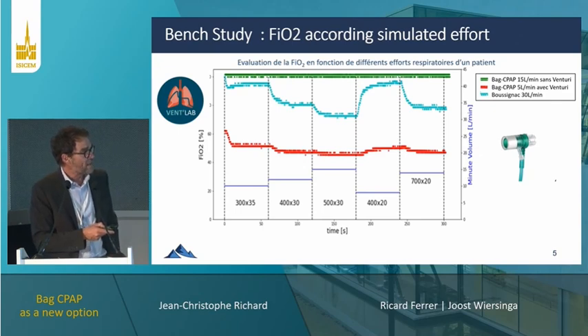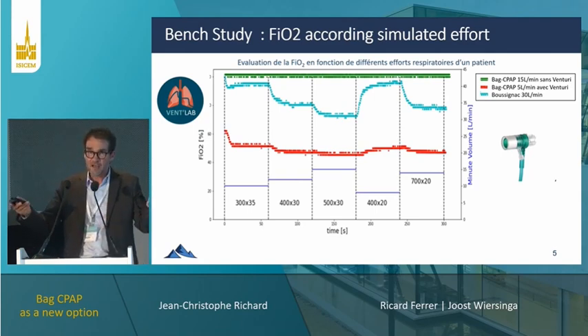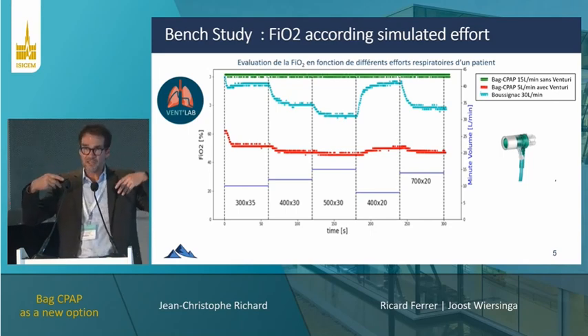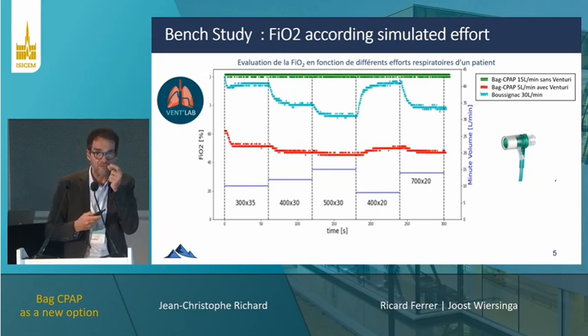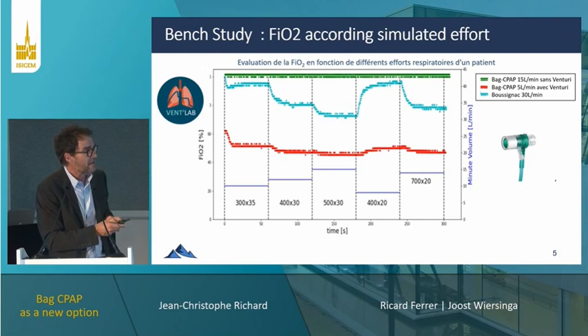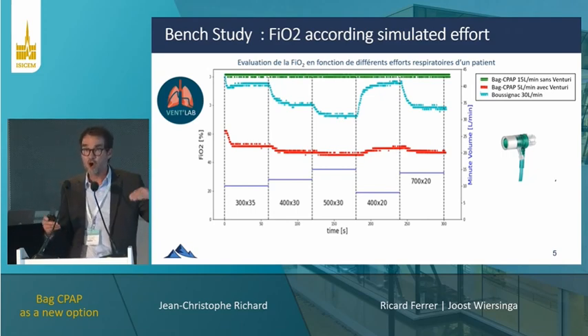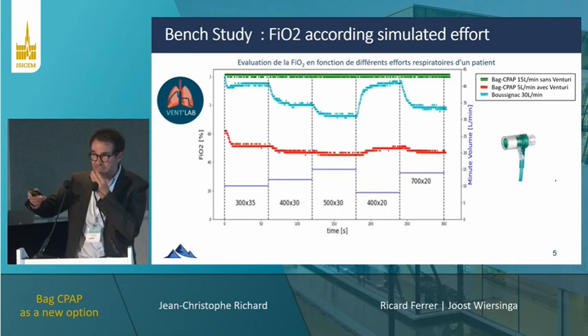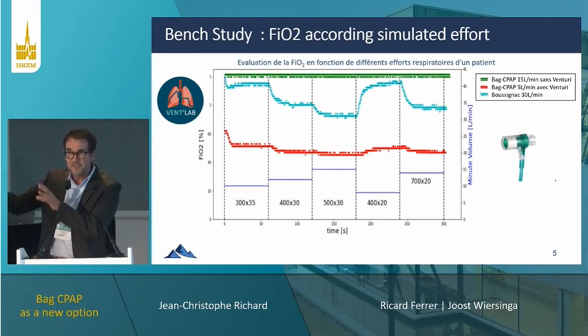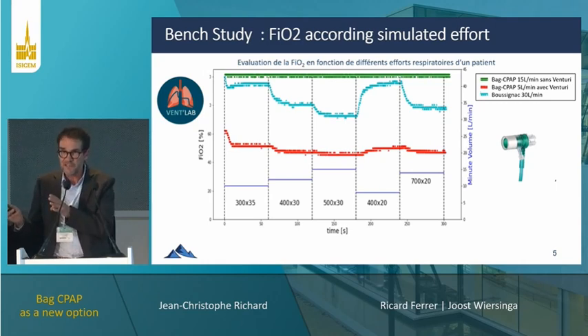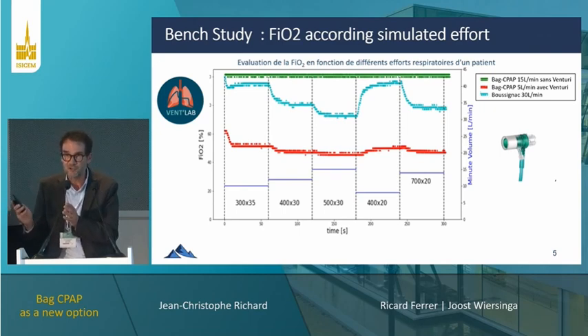And you can see that with the Boussignac system, the open valve, this is the blue line, the FiO2 is very high, but there is a drop in FiO2 as soon as the demand increases. It is just the result of the entrainment of ambient air when the patient is in respiratory distress with the open valve system. On the opposite, with the bag, you can see the green line with the high FiO2. The FiO2 is completely maintained, whatever the demand, above 90%, just because the patient is breathing the mixture from the reservoir. And if the reservoir is not empty, the mixture is guaranteed and the FiO2 is absolutely guaranteed.